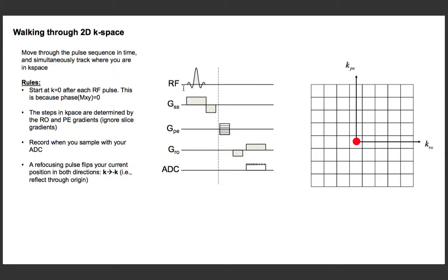So as I fill in my K-space in this example, we're only going to look in the phase and readout directions. The slice selection is through plane in K-space. So we only have a two-dimensional K-space, and we assume that the whole object, after we excited a slice, is all the signal needed to encode an image, available after that slice selection.